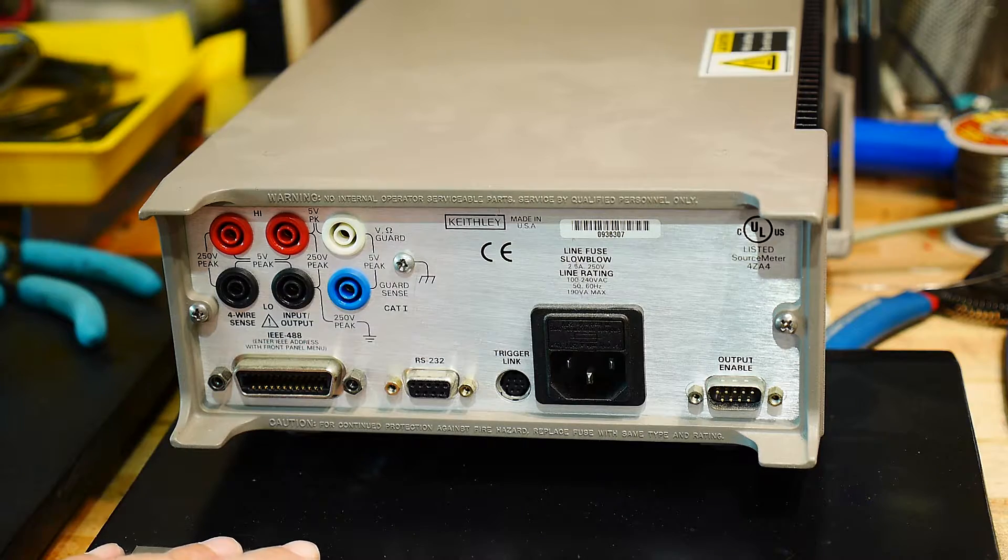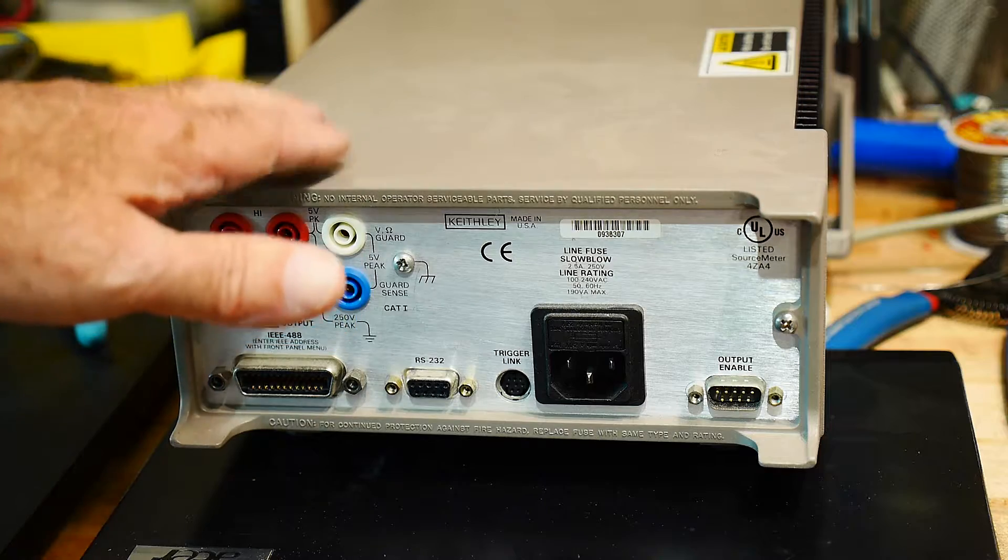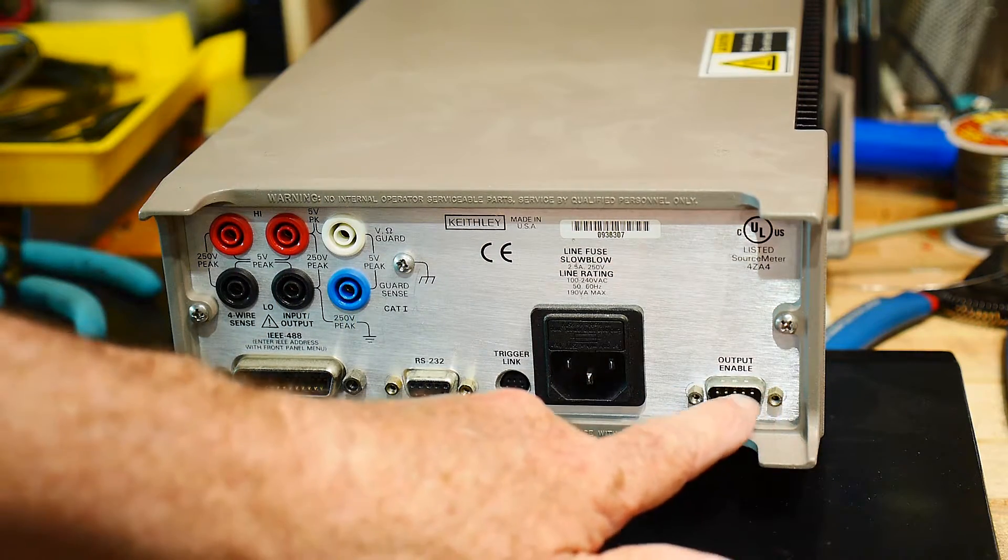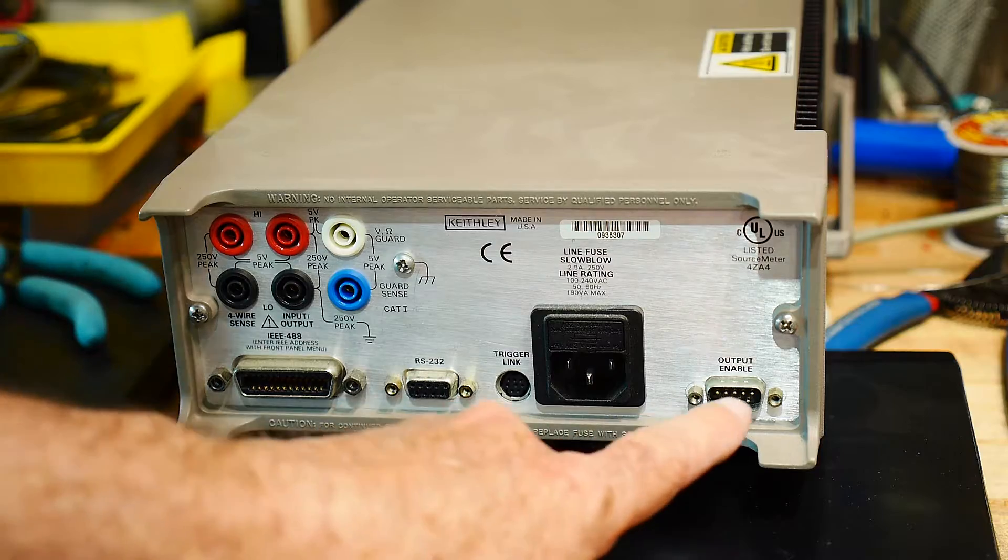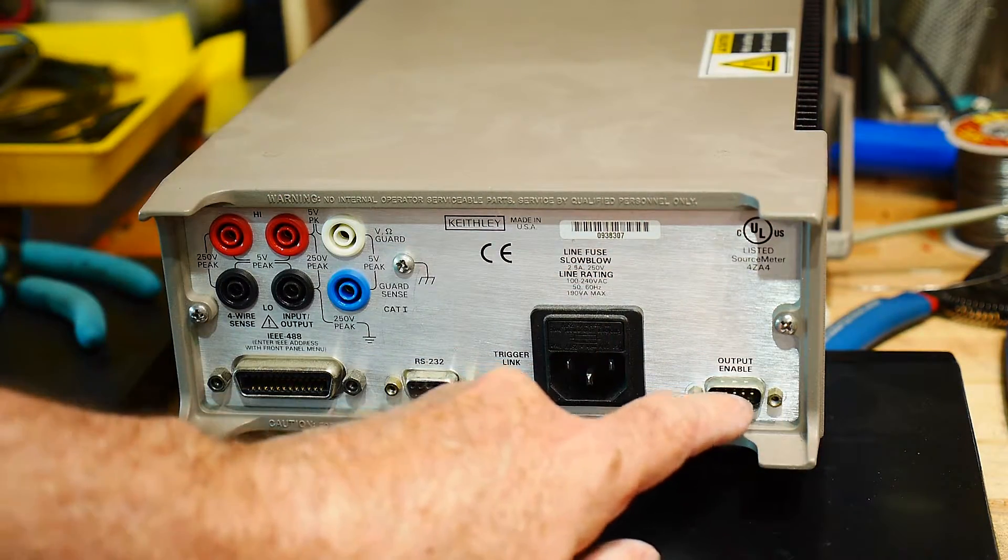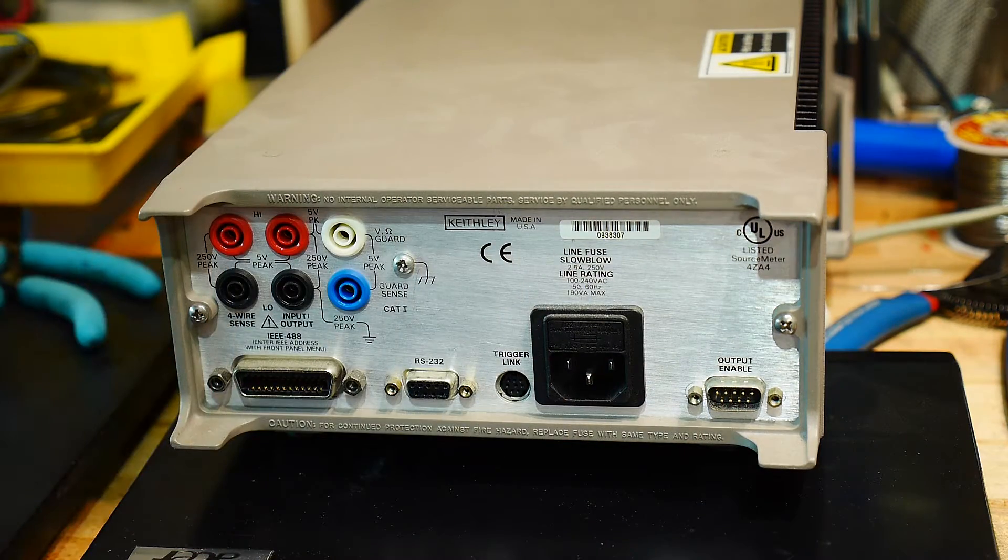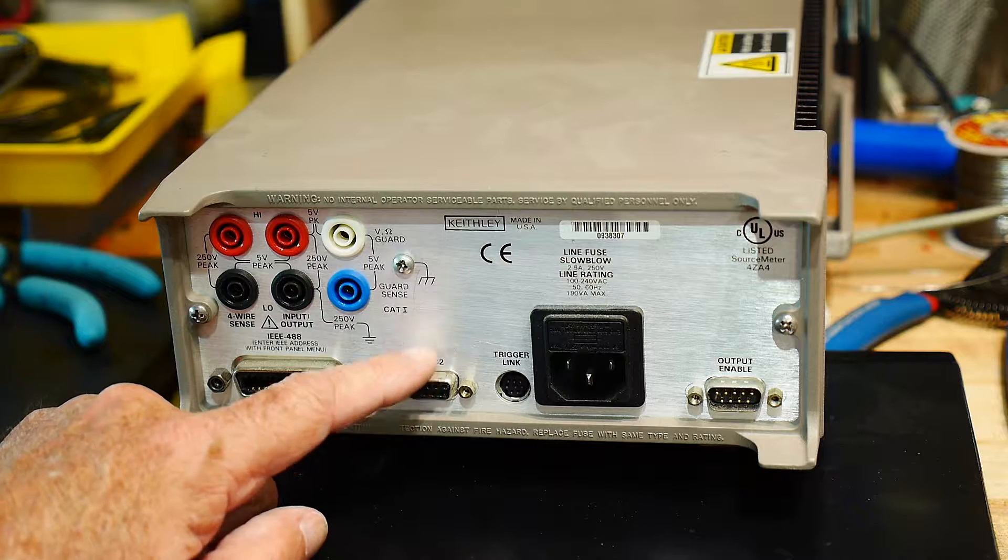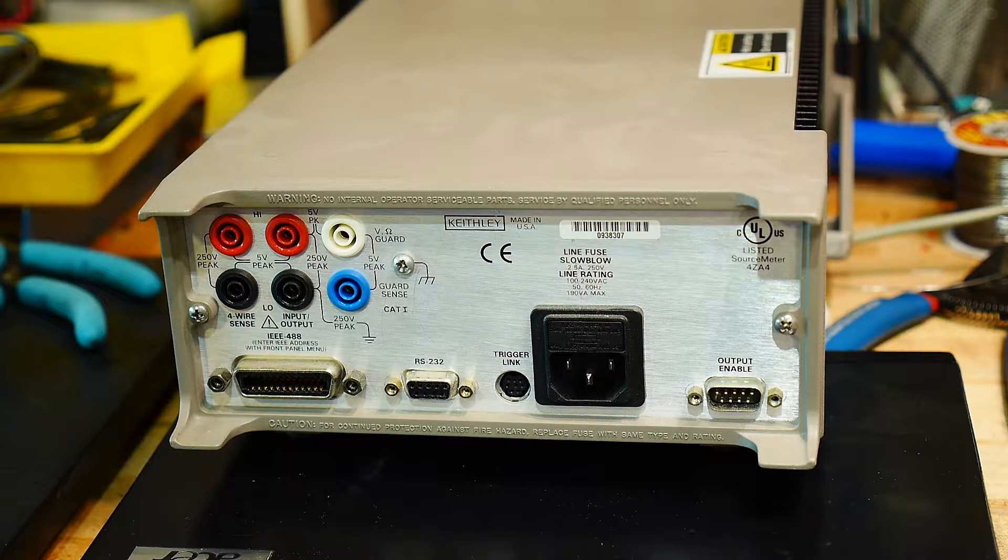We have some handshaking signals called output enable so you can safeguard this thing. I think if it kept putting out 200 volts it's a bit dangerous. So you can have interlocks and stuff on the output enable. You can have like a cover on your test equipment with a switch and the output can't enable itself unless the switch is closed, which is how that's used. There's a trigger. I've never used that. And then there's two ways of programming this thing, either IEEE 488 or RS-232. So we're going to use the RS-232. It's much easier and that's all you need to know.